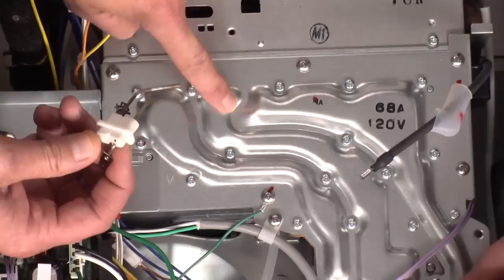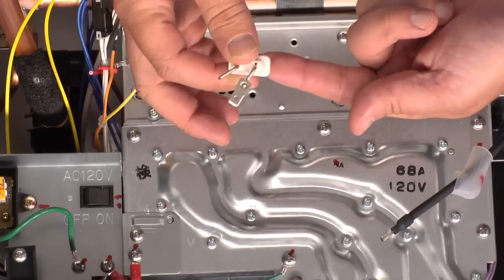Now the AFR rod is there to measure the combustion, our air-fuel ratio. You'll notice it's a smaller, straight rod, so it's over a specific section of the burner, where the other one's catching. Each burner has a high and low fire, so we're measuring a specific current there, and we know what that should be—that's how we know the combustion values.